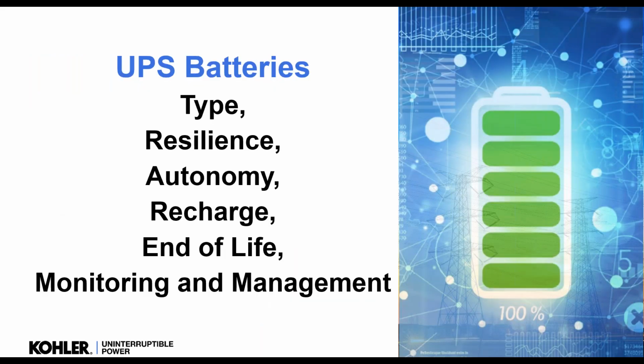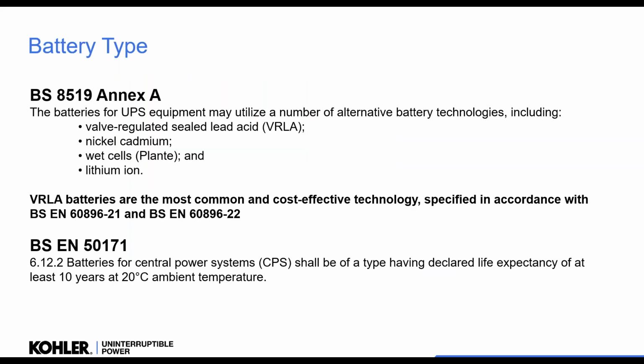So batteries, again, lots of different types, different resilience, different autonomies. We've got to consider the recharge, end of life, monitoring and managing of these batteries. Annex A of 8519 does talk about this. It talks about VRLA, NiCad, planté, lithium ion, but it recommends that the most cost effective is the VRLA. This is very much because these batteries tend to be long autonomy, whereas the other technologies, especially lithium, are in their element when they are for short, fast discharges on a regular basis. A life safety system is going to sit there, hardly being used except for testing, hopefully, and then have a long, slow discharge. That's where the lead acid is a good battery and very cost effective against the other types.